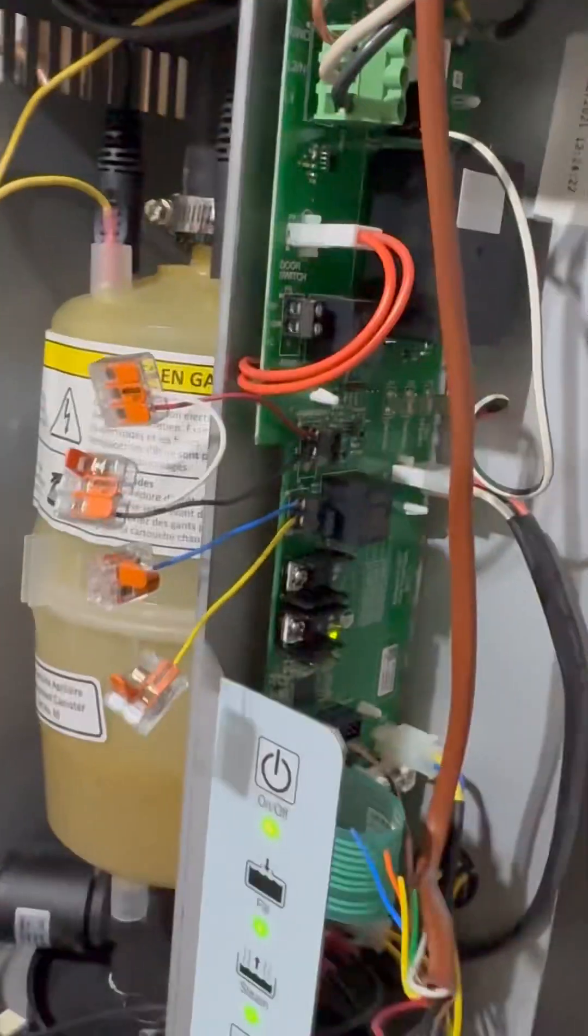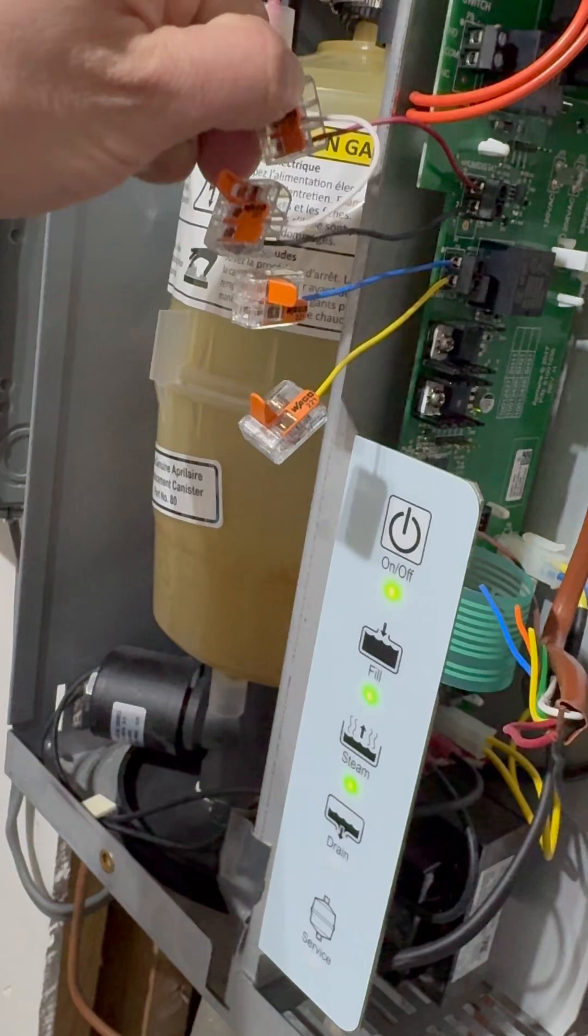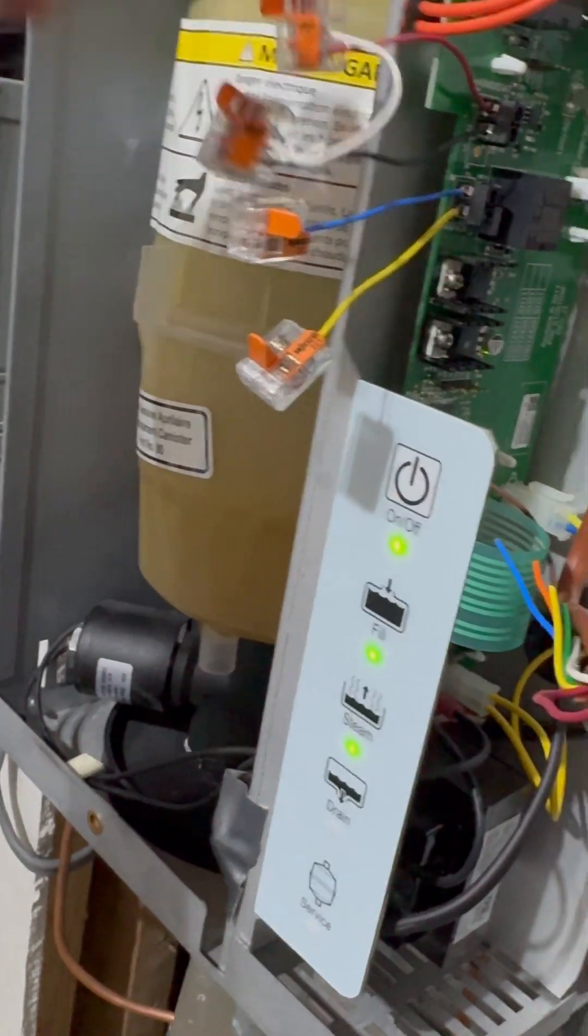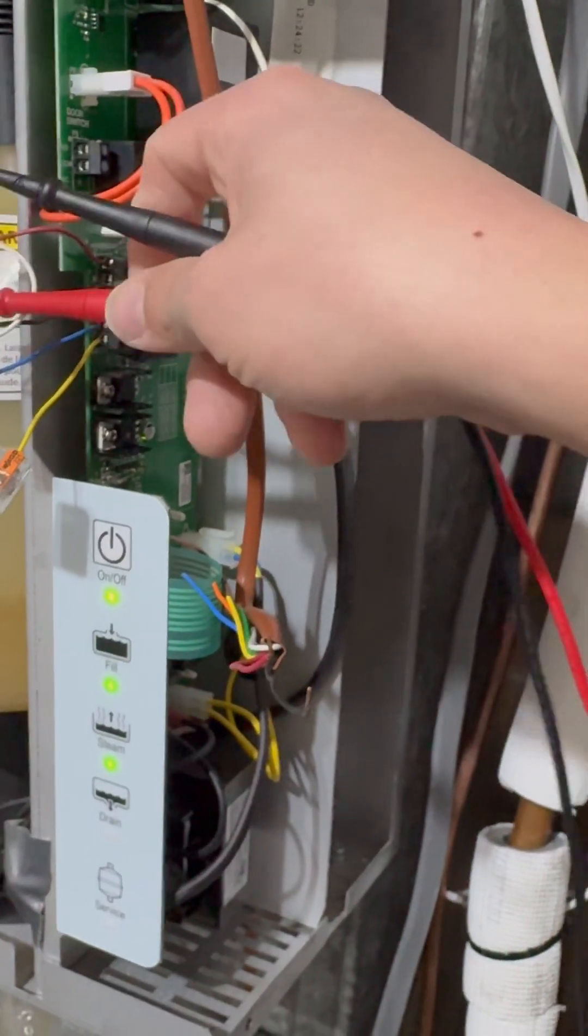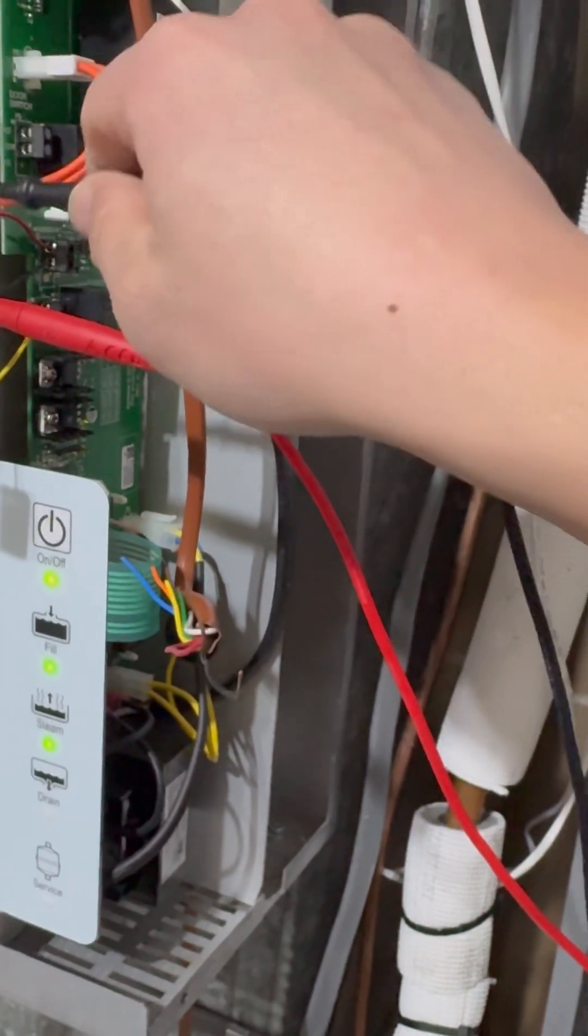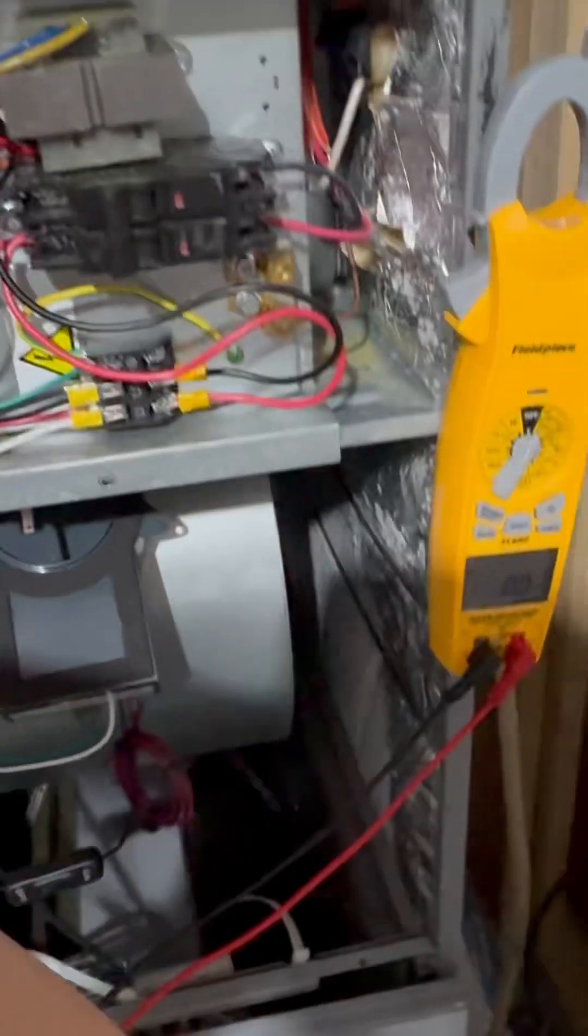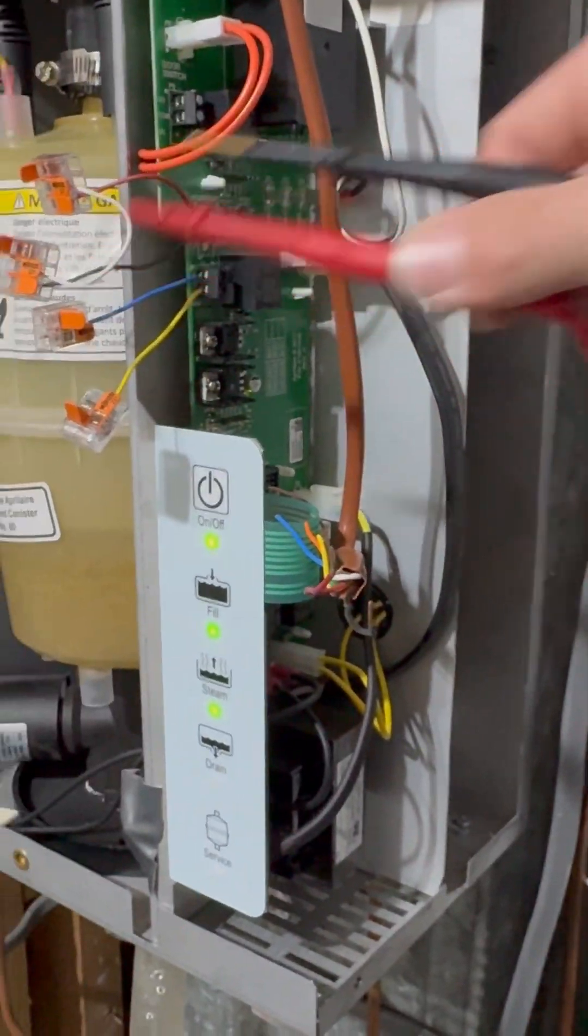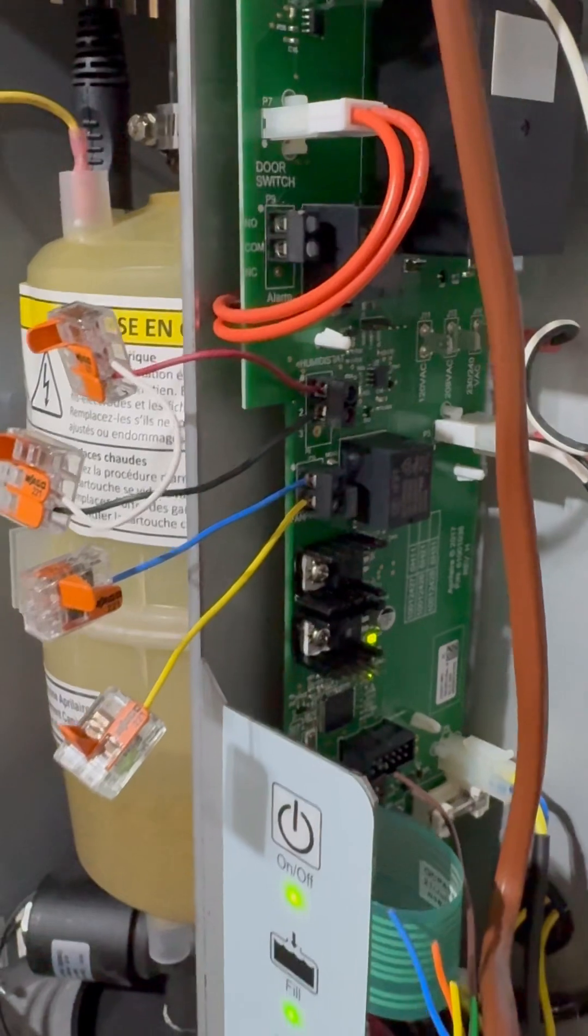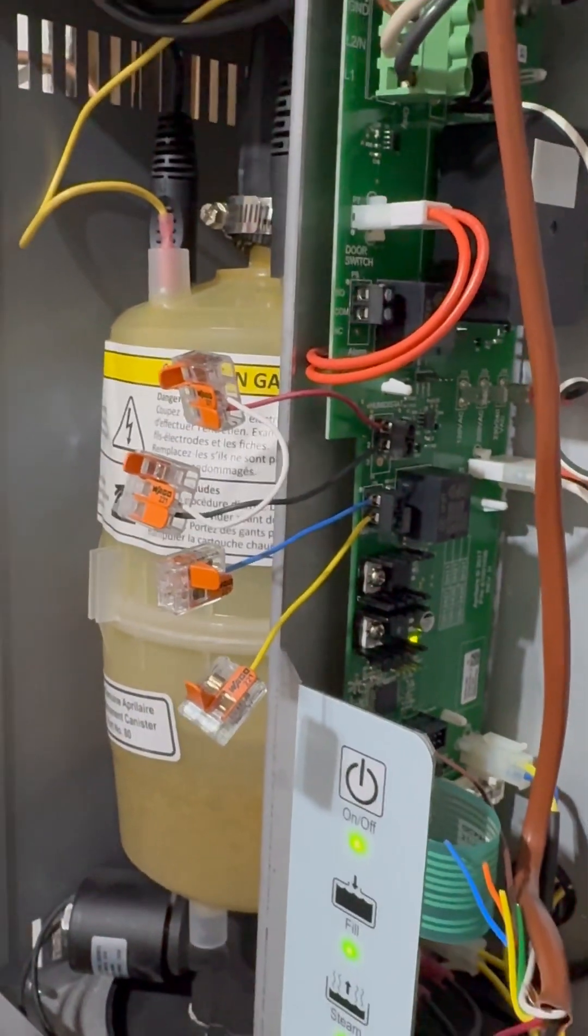That there's no voltage there, so I'm going to put my prong right here. Zero. Okay, so you wouldn't apply any voltage to the humidistat one and two terminals - you could damage the board.